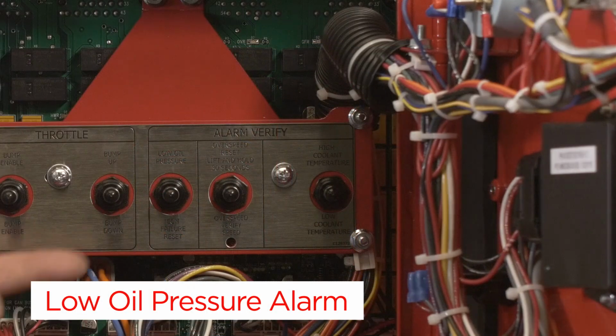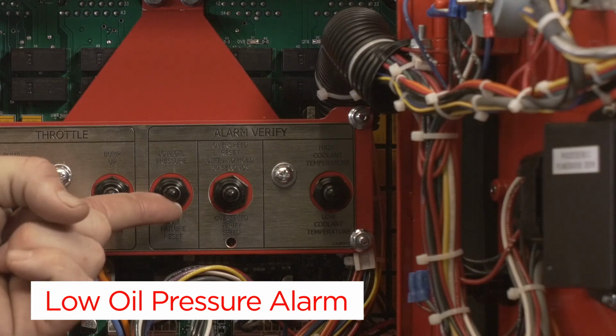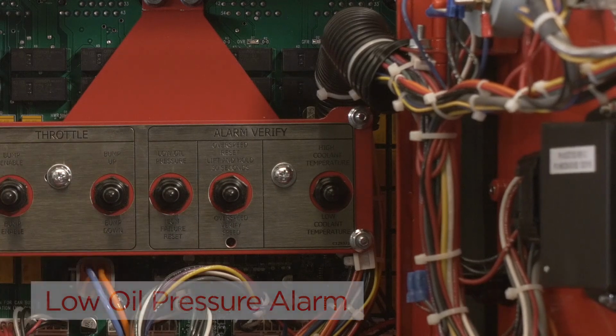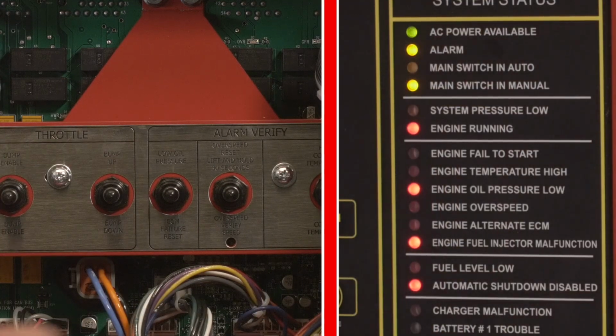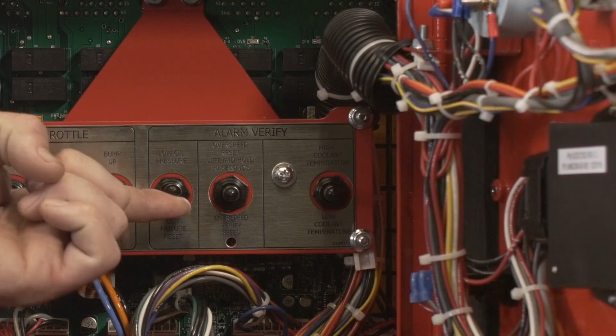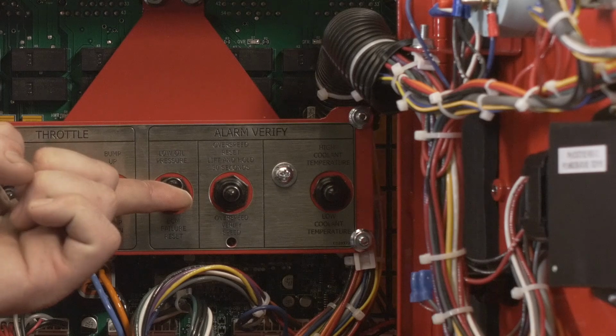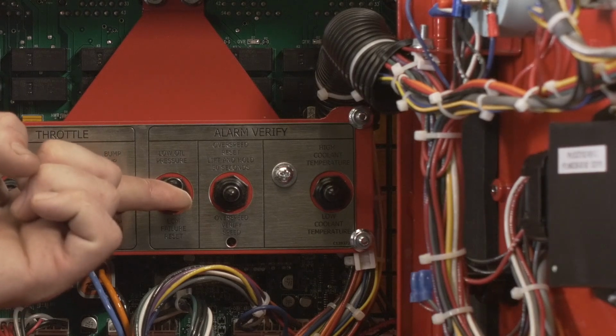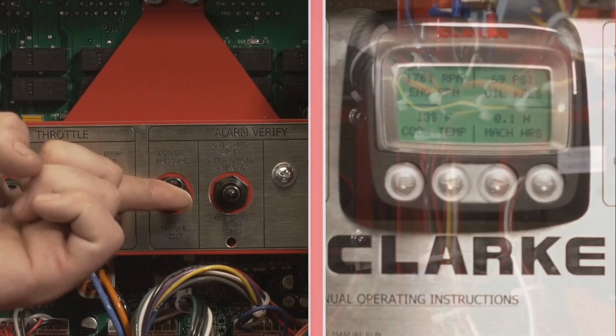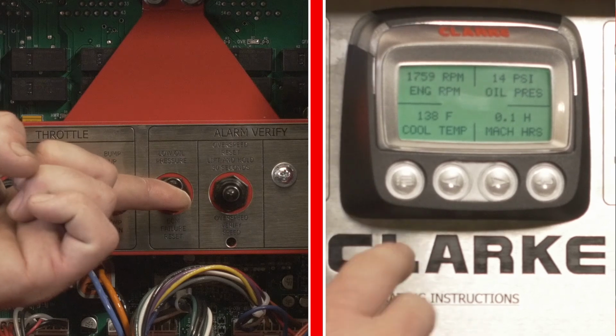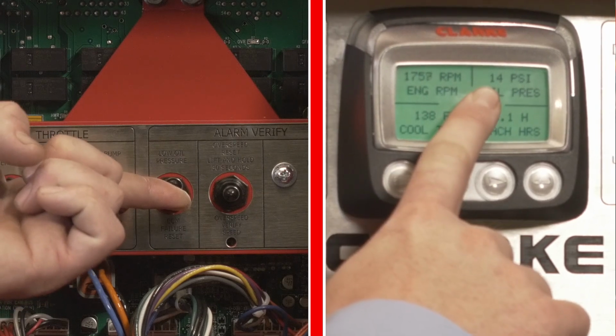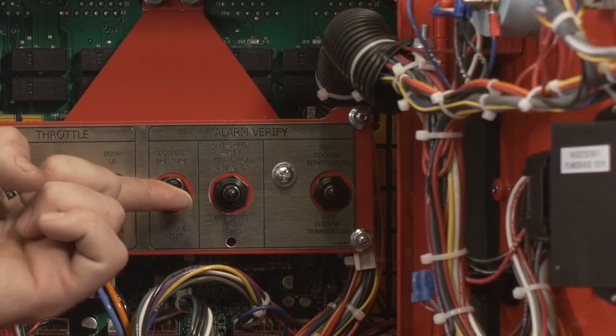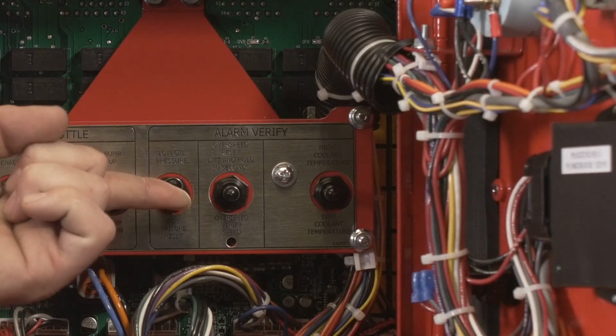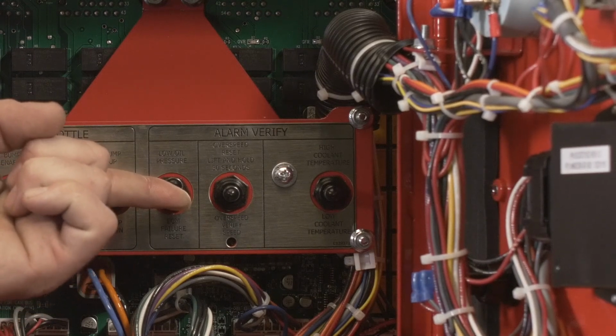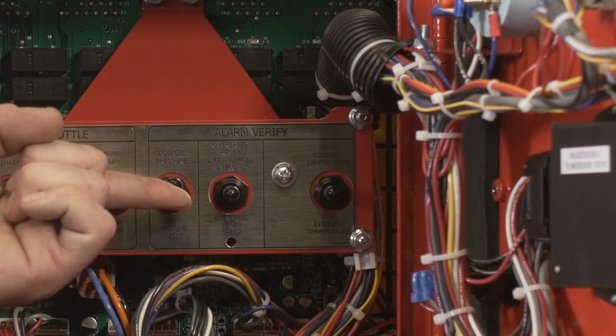The low oil pressure alarm verification is a momentary position switch allowing you to simulate the oil pressure alarm. It's located on the switch plate inside of the Clarke panel. With the engine running, lift the switch to the up position. The oil pressure signal will be defaulted to less than 20 psi and can be seen on the engine digital display. Continue holding the low oil pressure verify switch for 20 seconds until the alarm is indicated at the pump controller at terminal 4.